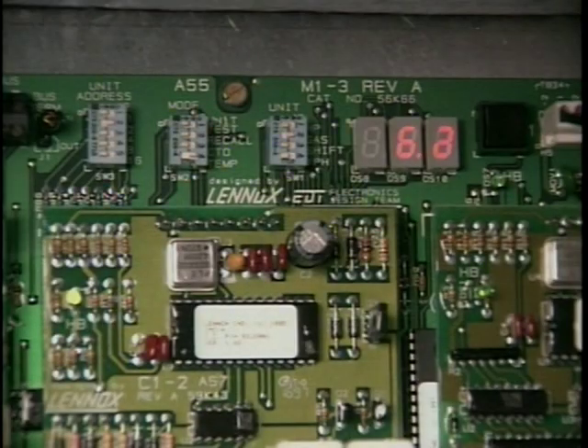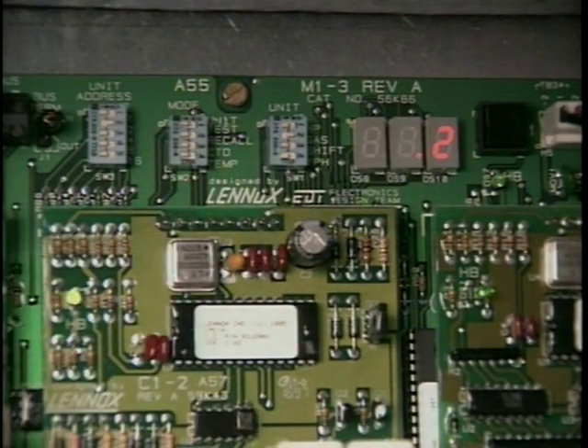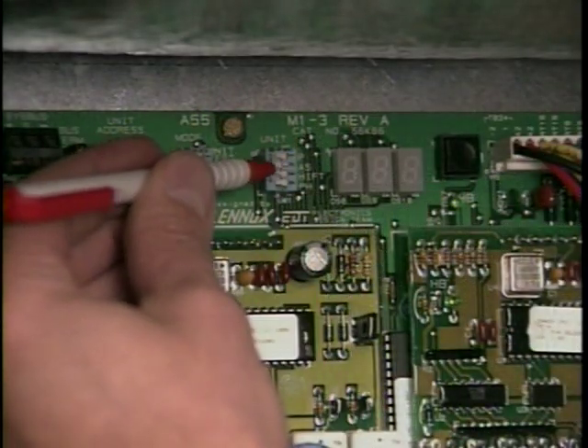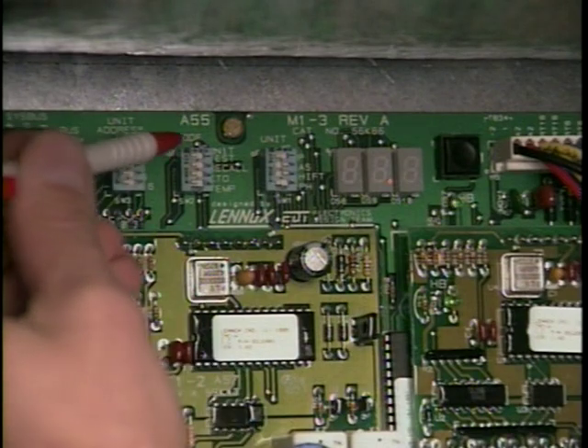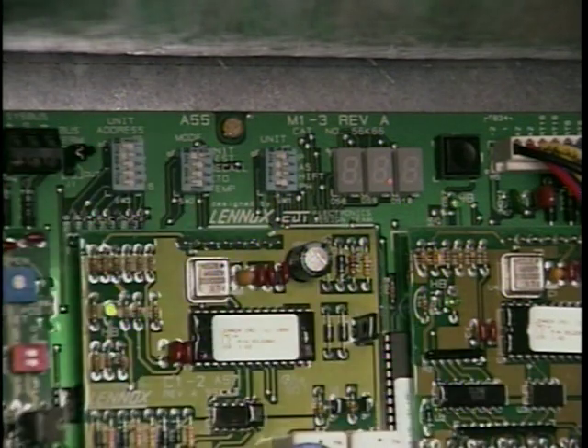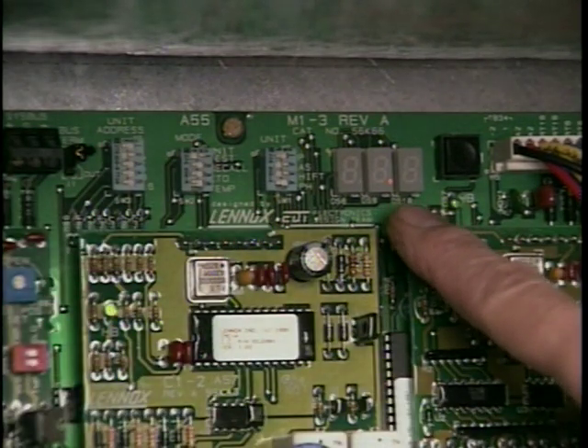Record the cooling supply air temperature in space 53. After recording the temperatures, place switch 4 on SW2 off. Place the system in full heat with the IMC board by placing switch 3 on SW1 on and placing switch 1 on SW2 on. The switches must be operated in this order.